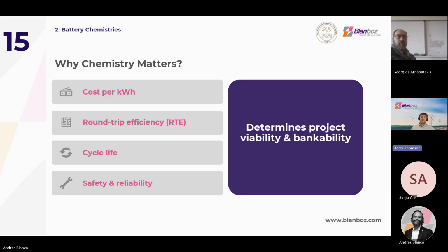Next we have the round trip efficiency - how much energy you're losing between a full charge and discharge cycle. This matters because small round trip efficiency differences compound significantly over thousands of cycles, especially for large projects. Lower RTE reduces the delivered energy and reduces the overall revenue that can be earned by the BESS.